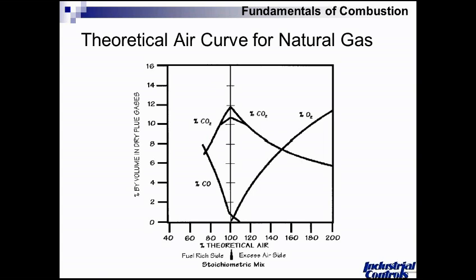You'll see that CO2 peaks at the theoretical point of 12 percent for natural gas. As you drop the air available or add more fuel, that value drops off. That's one of the many reasons we don't trim based on it because in this scenario you can't tell which side of the stoichiometric ER by simply looking at CO2. We generally look at CO and O2 and other gases when looking at it from an emission standpoint, but CO and O2 are basic needs to measure when setting a burner up.